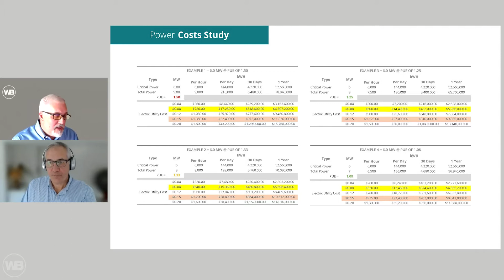We're using a 1.5 PUE versus all the way down to a 1.08. As you can see, even at 8 cents a kilowatt hour, which we see some of our clients in, it's $6 million a year to run your facility. If you can reduce your PUE down to 1.25, you're going to save $1 million a year. So that's a lot, and really that's kind of what we wanted to show here. We'll share this with you guys, and if you have questions we can talk about it later.